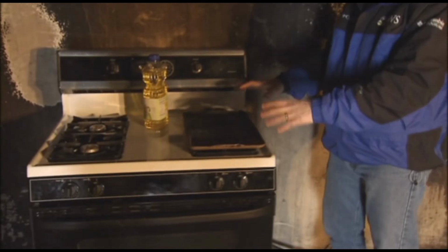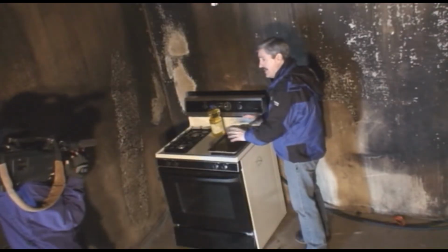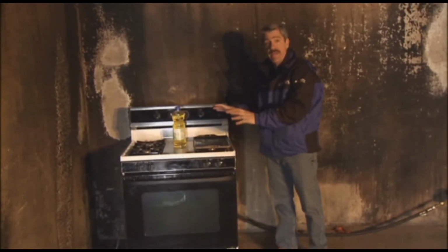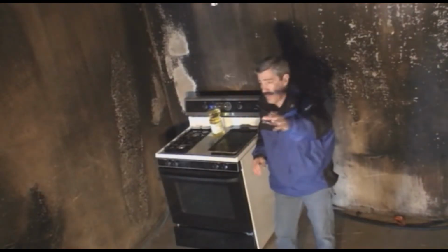For the purposes of our test, we've got a stove here with a hot griddle. It's going to have some grease on it, and we're going to see what happens when it catches fire. Right here we have the sprinkler nozzle where the solution is going to come down over the stove to see if we get a flash. Now we've set up cameras in several places, so you're going to get a good look at what happens.